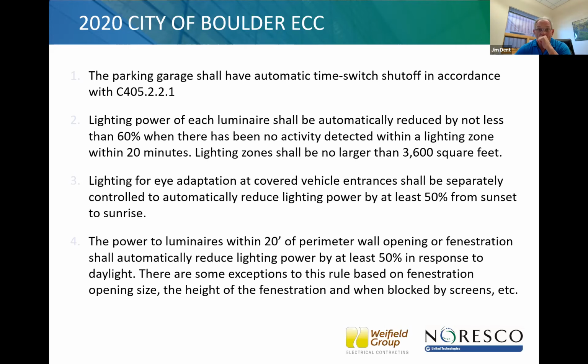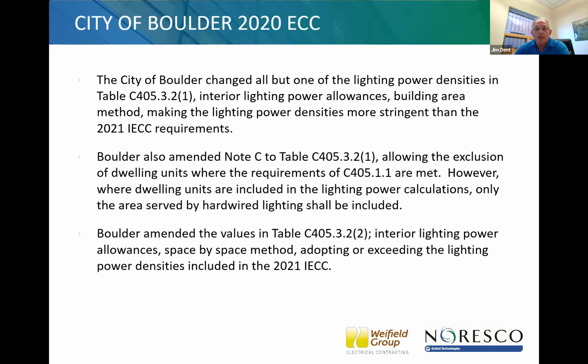Next, Kevin. The city of Boulder changed all but one of the lighting power densities in Table C405.3.2(1). That's the interior lighting power allowances for the building area method. So the lighting power densities in the City of Boulder 2020 Energy Conservation Code are considerably more stringent than the 2021 IECC or the 2018 IECC.